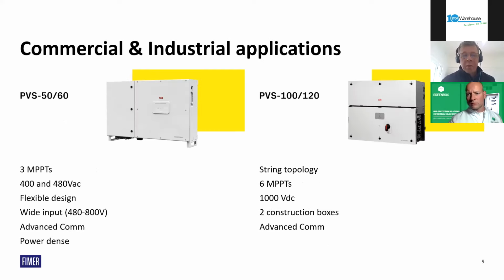In the C&I space, we have the PVS 50, PVS 60, PVS 100 and PVS 120. The PVS 50 has a few different ranges - the top model is a 3 MPPT model, and we also have a single tracker version. You'll see the 400 and 480 volt differences there. The PVS 50 and PVS 100 have a nominal AC voltage of 400 volts, so that can be connected to standard LV. The PVS 60 and PVS 120 have a nominal AC voltage of 480 volts, used more in project situations where it's connected to a step-up transformer and directly to MV like 11 and 22 kV.